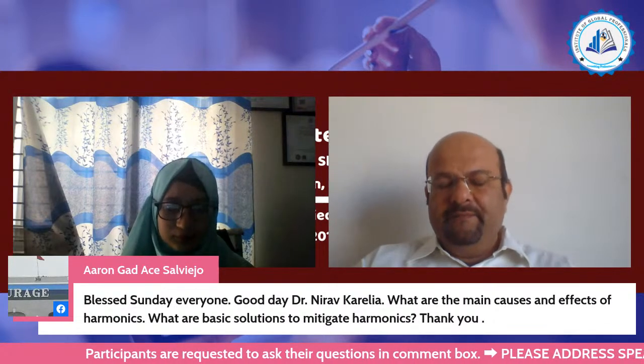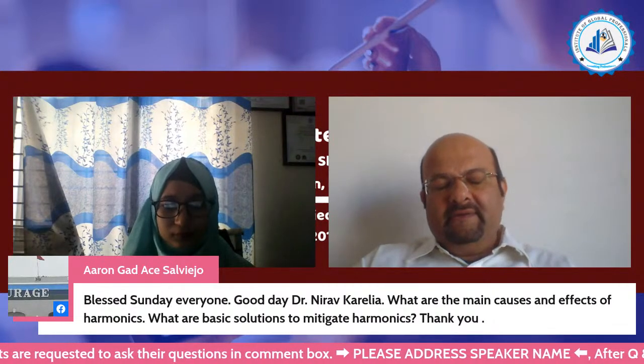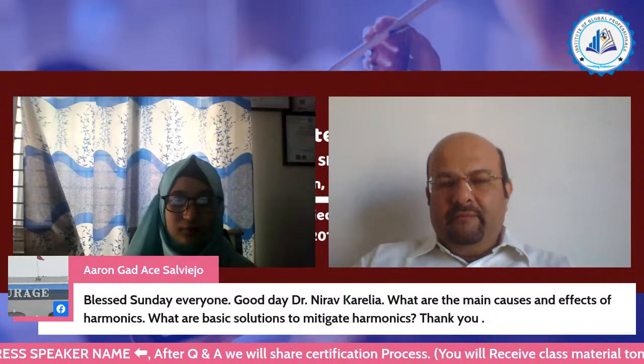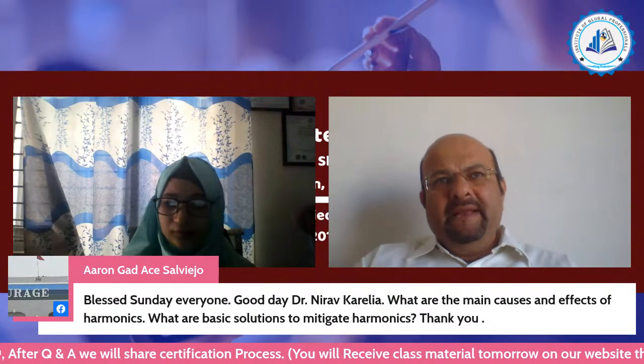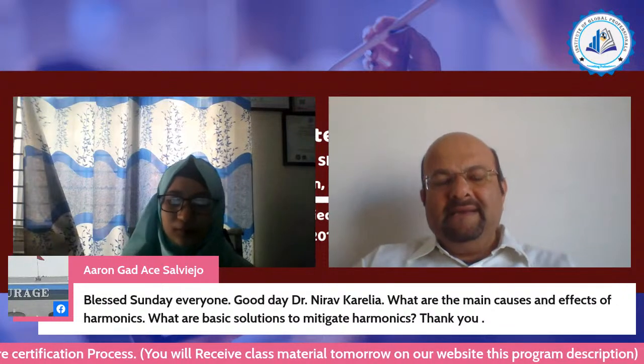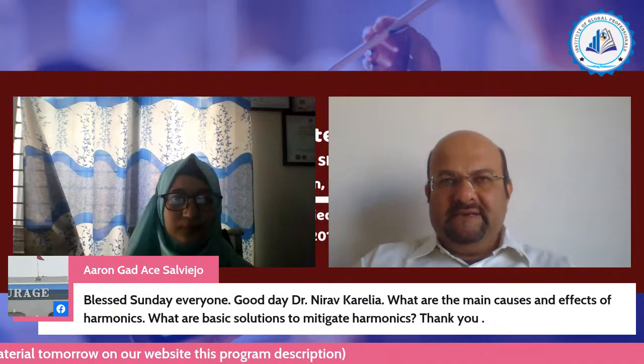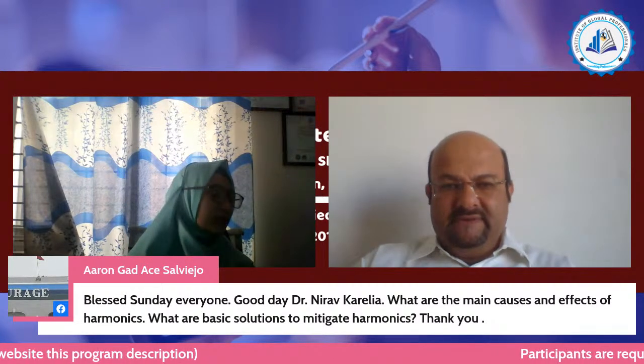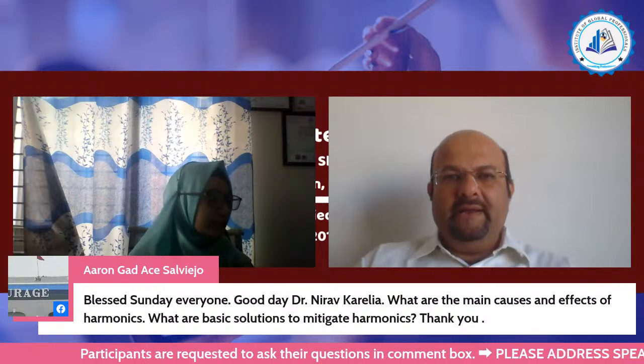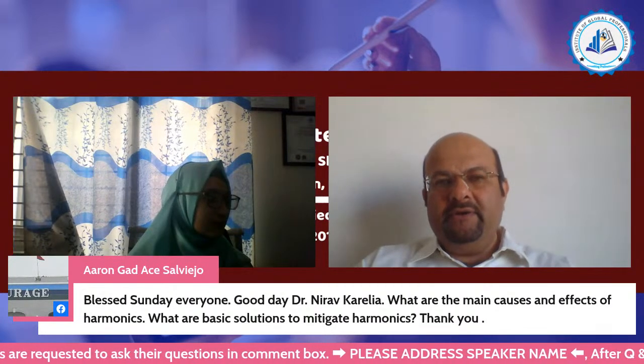During the charge up of a transformer, when it is charged, we traverse through the non-linear part also, and that will distort the waveform, meaning it introduces harmonics. Apart from this, there are many instances of continuous switching, particularly power electronic switching, where very high frequency switching is used. Whenever such switching takes place, a lot of non-linearity is introduced, meaning it will introduce harmonics.